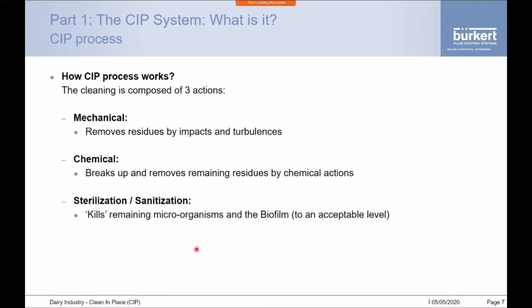CIP is composed of three actions. The first action is mechanical — generally the first step of the CIP process — where we have a pre-rinse step using water at high velocity. We use the turbulence within the water to remove most of the visible solids, anything still coating our pipework or vessels. We then use acids or bases, which is the chemical step, to start breaking up and removing remaining residue by chemical action.